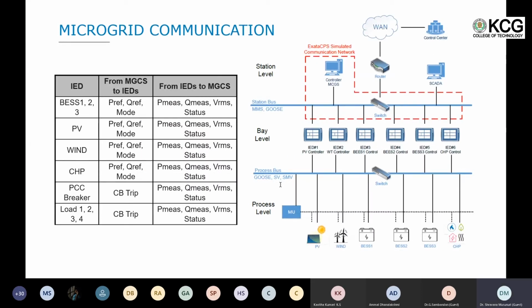So basically we have three levels defined: at the station bus or station level we have the microgrid controller, which interfaces through the network switch at the bay level to the virtual IEDs, and these virtual IEDs interact at the process level with the models of the PV, wind, and other systems.